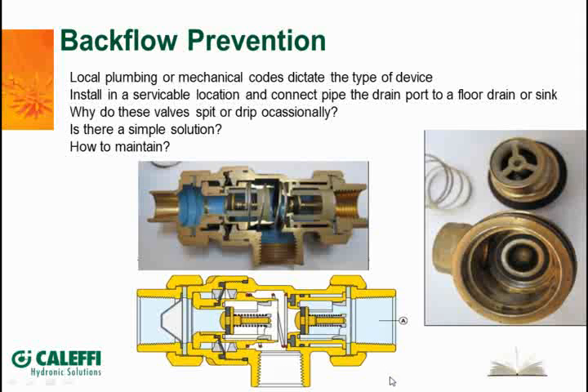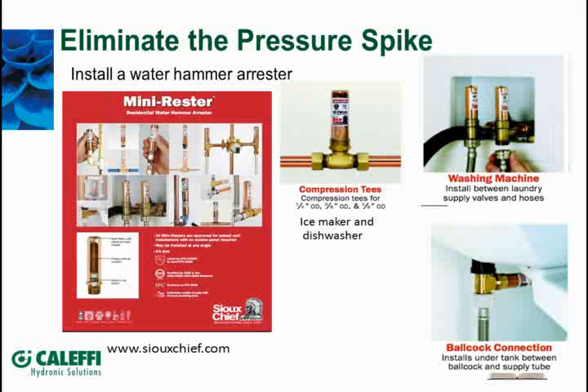And one of the things that causes that to happen, and I've had installers tell me some little tricks for diagnosing and also fixing this, is a pressure spike or a surge or a low pressure condition out on the main. Maybe there's a fire down the street and somebody opened the water hydrant and the pressure dropped in the main, caused that valve to come off and seal. Well, if that valve does that over and over and over again, you're going to get a little bit of a buildup between that sealing surface on that O-ring and the end of that brass spool in there, and then it's not going to shut off tightly, and it's going to drip, drip, drip, and it's not going to stop dripping until you get in there and clean it out.